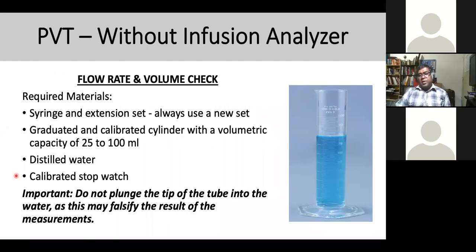These are performance verification tests. Without using an infusion analyzer, you can use a syringe and extension set. Always use a new set and a graduated calibrated cylinder. Volumetric capacity is somewhere between 25 and 100 ml. And distilled water, and a calibrated stopwatch. And important, do not plunge the tip of the tube into the water. It may affect the results of measurement. It's very important that you don't put the tip in the water, all that.